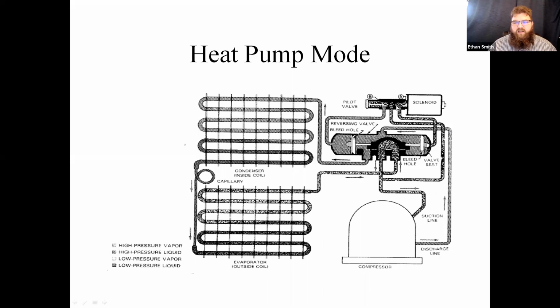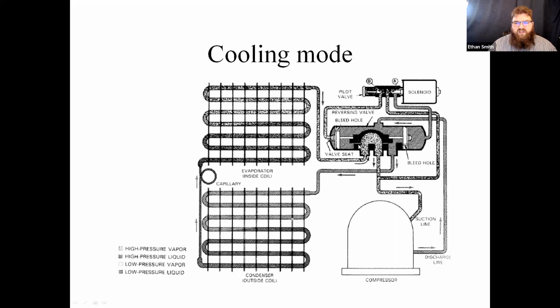It has a clamshell in it, okay, that controls which side of that valve is exposed to the suction side of the system and which side of that valve is exposed to the high side of that system. So a modern valve is going to have a high pressure line into it, and it's got a suction line into it as well. So what this solenoid does is it moves its internal clamshell back and forth over these three pipes on the bottom. And you'll notice that the two side pipes go to the two sides of the reversing valve. So when we want to change modes on this thing, we are just going to change the position of that clamshell.